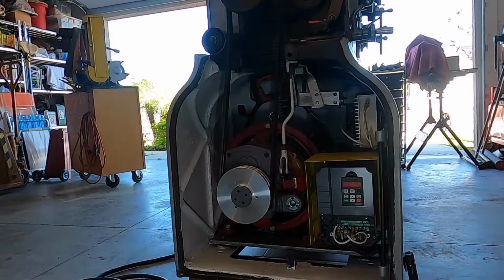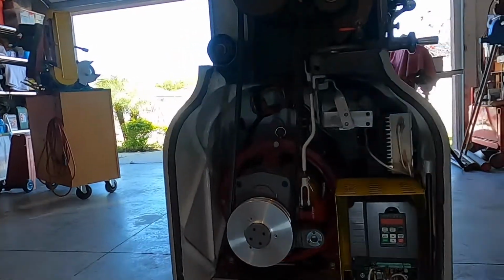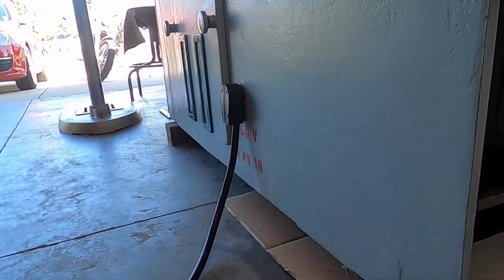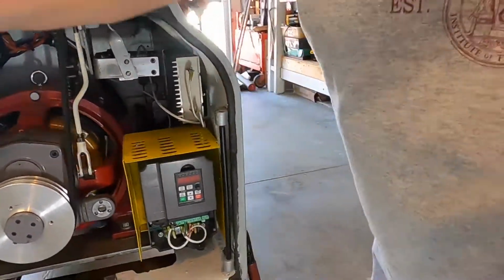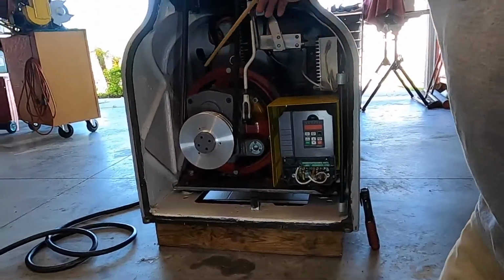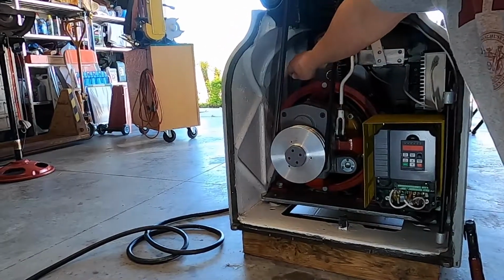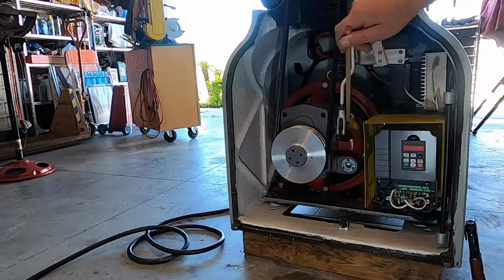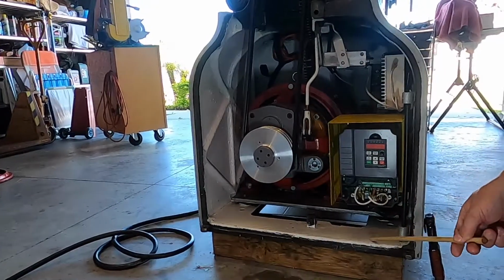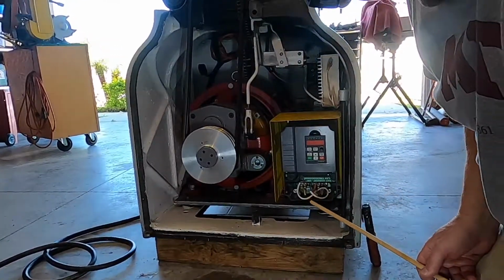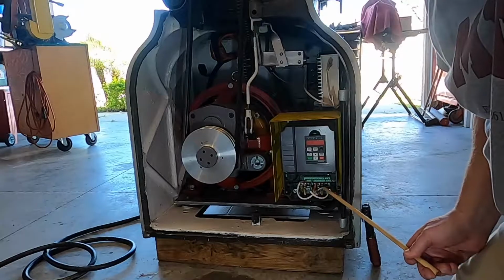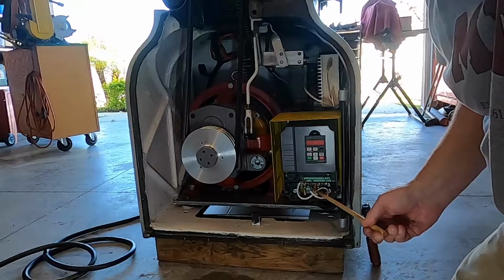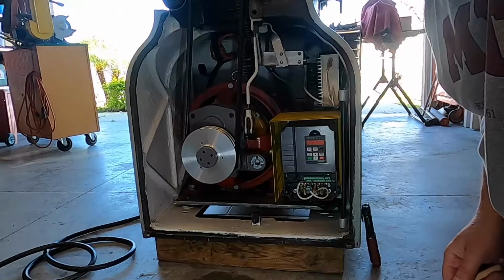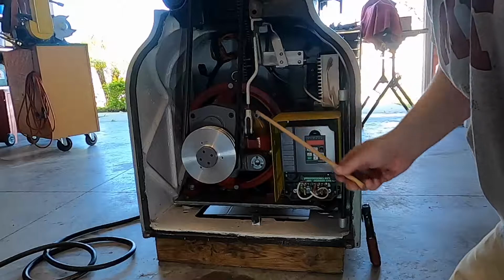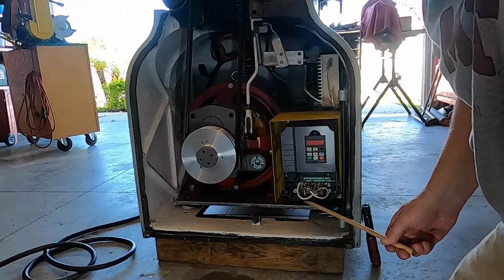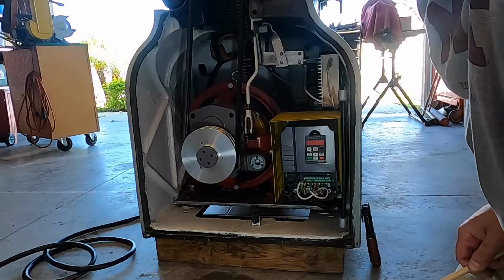With the Huanyang, it's very simple. I showed you the wiring coming in on the side down here. I've wired it so I have my receptacle back here and the cable coming over, up, and through into the Huanyang down here. So you have the input - hot, neutral, and a ground. Then going out, because I have a three-phase motor, you have your three phases going straight to the motor. That's really all there is to it.